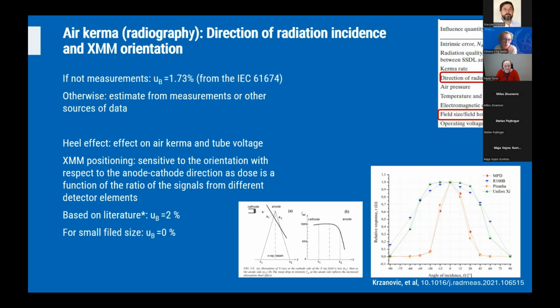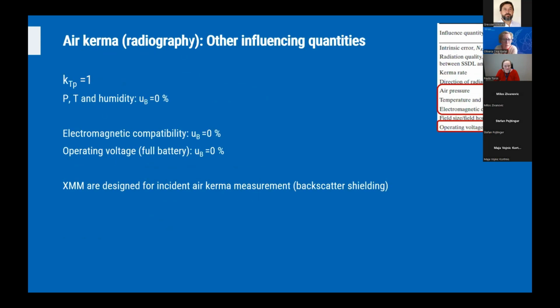As they contain a row of different semiconductor detectors covered with different layers of copper filtration, the orientation within the X-ray beam is also an important parameter, as the instruments can be affected by the heel effect. So as a rule of thumb, the orientation should always be perpendicular to the anode-cathode axis, and this orientation is very, very important in mammography, even more than in diagnostic radiology, of course. For smaller field sizes and better collimation, this effect is less pronounced. Other influencing quantities that should be considered and evaluated are pressure, temperature, and humidity, which is almost negligible in the case of semiconductor-based detectors, as well as electromagnetic compatibility and operating voltage, provided that the battery is full.